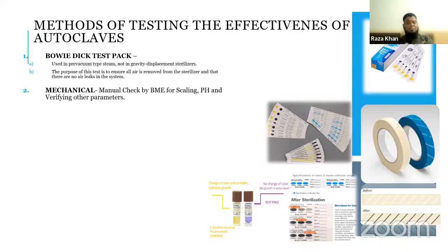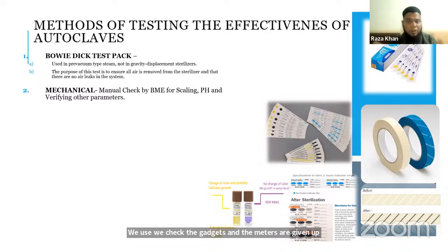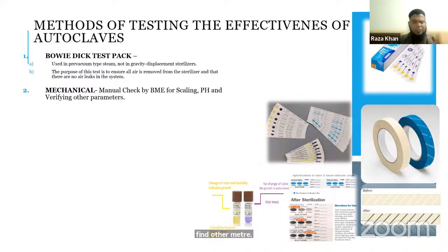There is also another important step in which we check our autoclave. That is a manual step. We check the gauges and the meters given on the sterilizer. We physically check the chamber for scaling. We check the pH of water, which is used for the autoclaving, and verify other meters. Usually, this process is carried out by biomedical engineers in a healthcare setup.